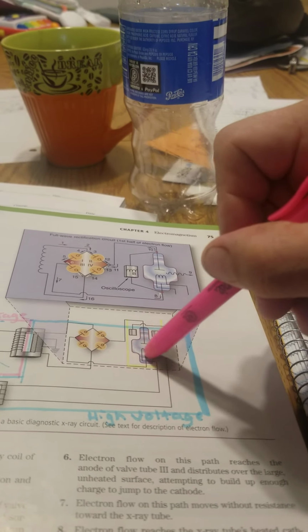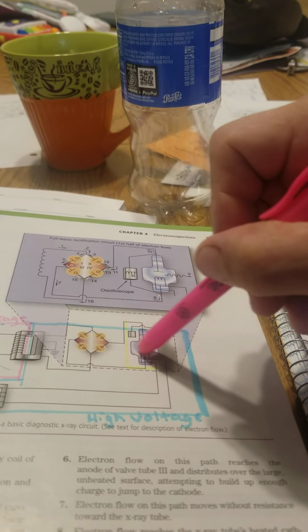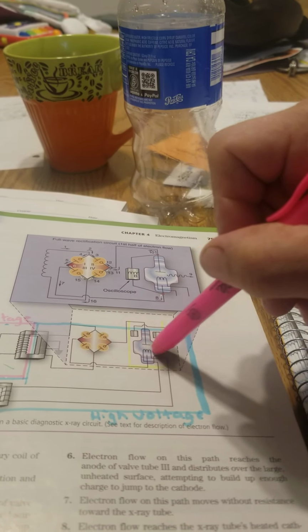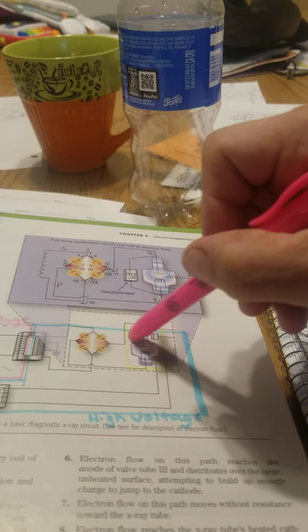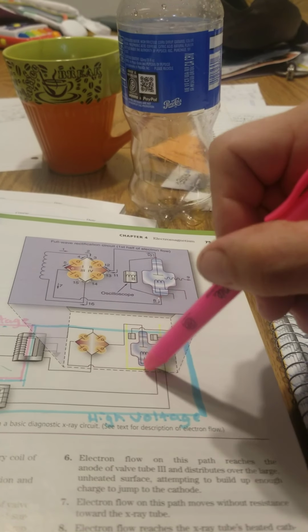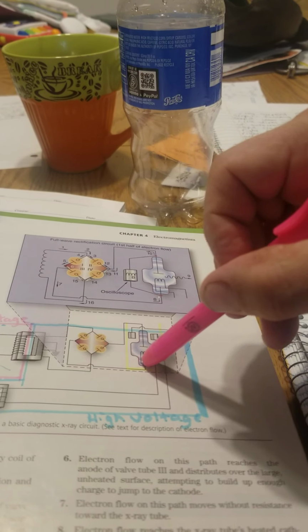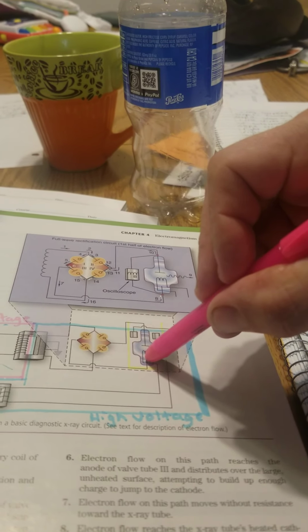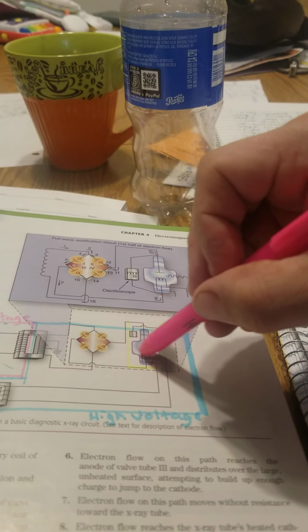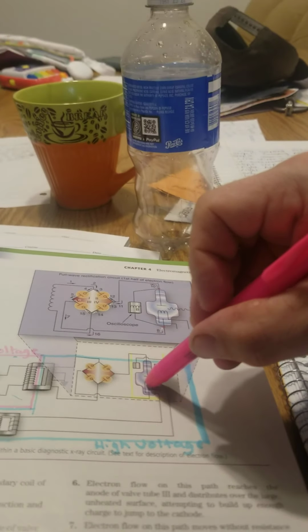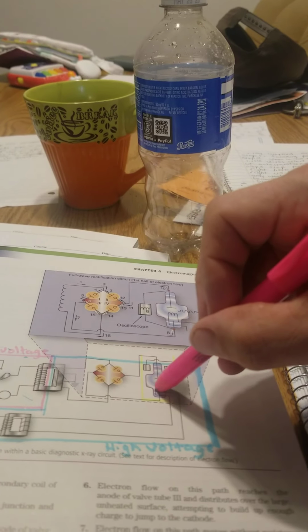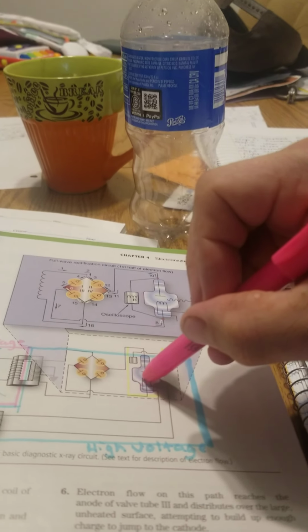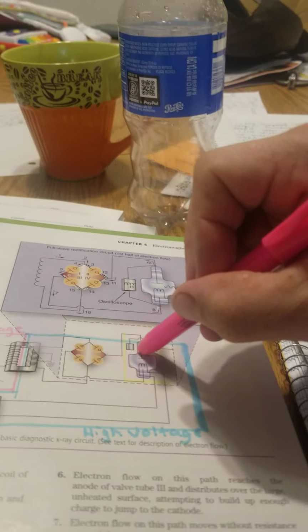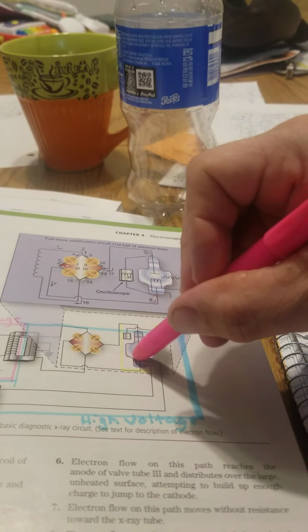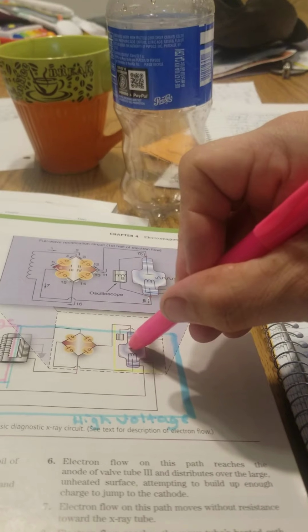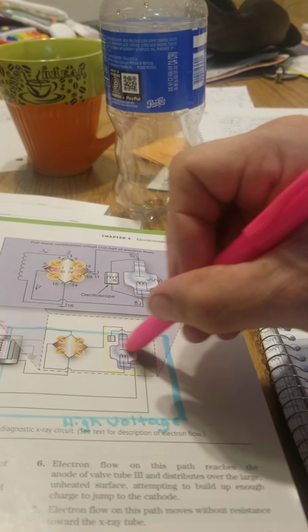And this is on the cathode side. This has a negative charge as well. It needs to make sure that this is a negative charge over here. And then over on this side, this is a positive charge. And when the current is induced inside the tube itself, the filaments within the focusing cup light up. And the negative charge repels the electrons, so they come flowing out, and they're being pulled over to the other side through the vacuum envelope of the tube itself to the spinning anode.